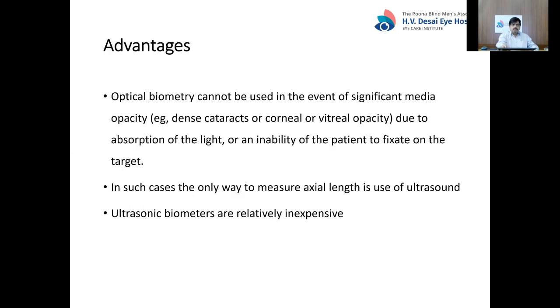There are advantages to A-scan biometry. In certain conditions such as a very dense cataract, dense corneal opacity, or vitreous opacity, an optical biometer cannot measure the axial length. In these cases, ultrasound biometry is the only option. Additionally, ultrasound biometers are relatively inexpensive compared to optical biometers.